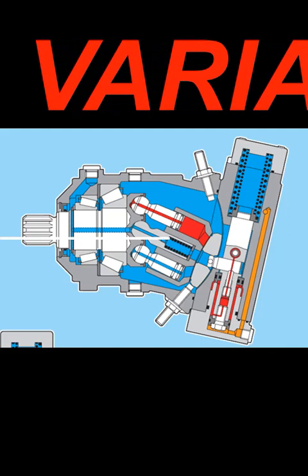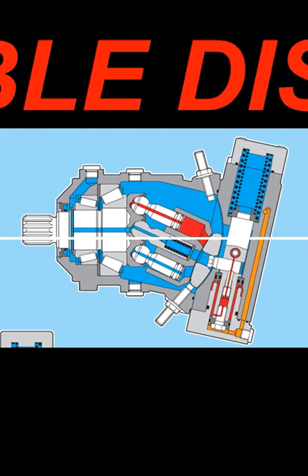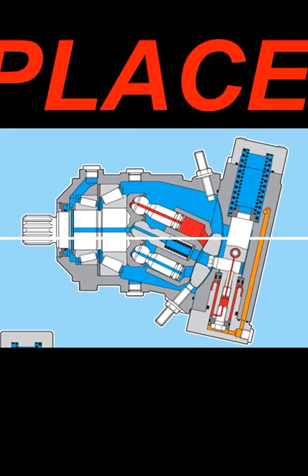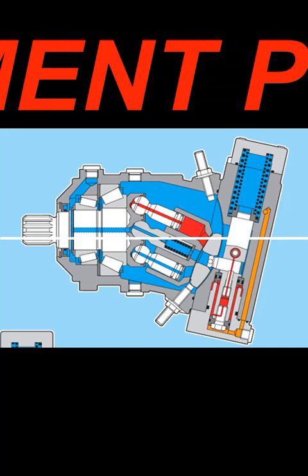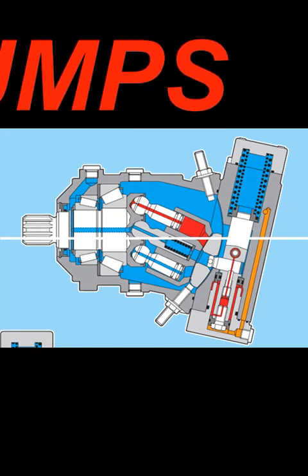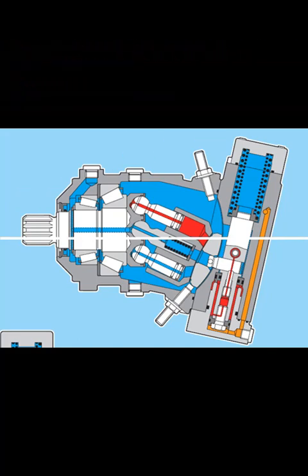Working pressure applies a force on a piston within the control piston onto a rocker arm. An externally adjustable spring force is applied to the other side of the rocker arm to determine the power setting. Should the working pressure exceed the set spring force, the pilot control valve is operated via the rocker arm, allowing the pump to swivel towards zero output. This in turn reduces the effective moment on the arm of the rocker, thus allowing the working pressure to rise in the same ratio by which the output flow is reduced.